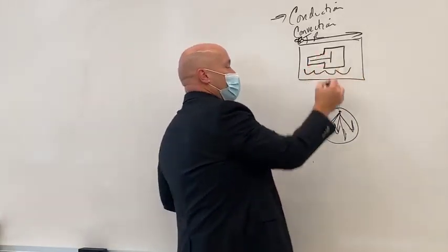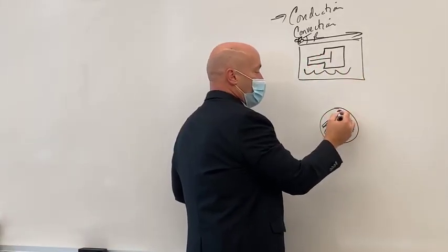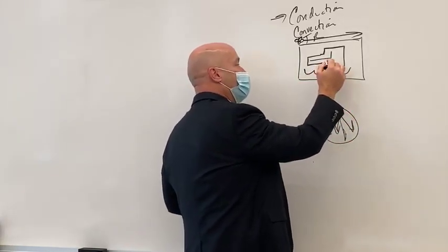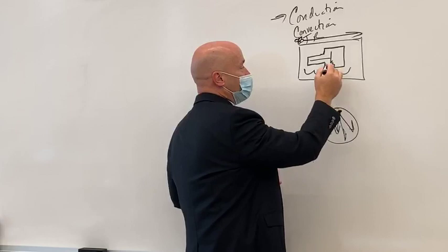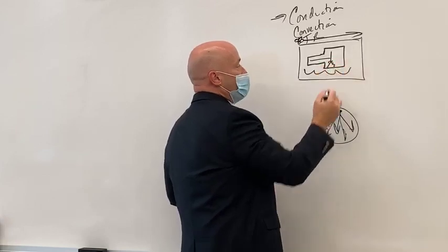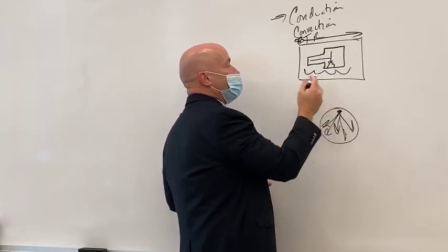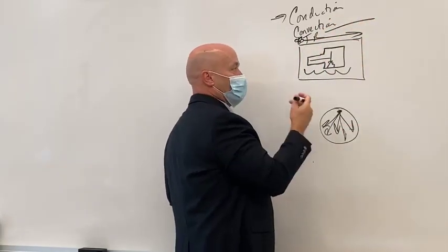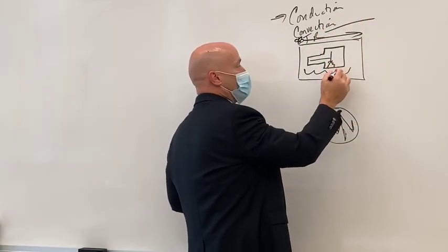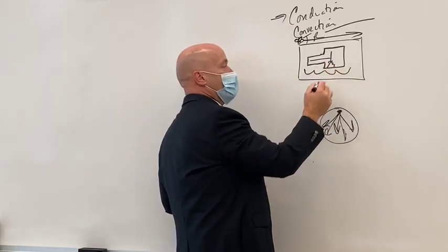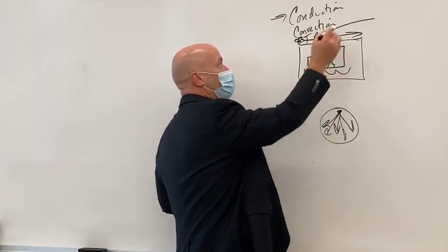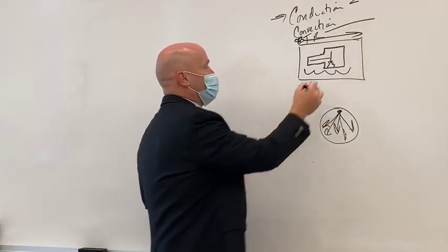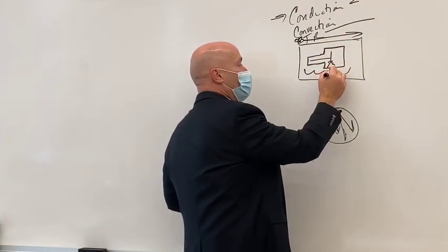And so we've got the conduction from the actual focal spot across the face of the anode, and then it's going to thermally radiate to the glass. And so that is your thermal radiation, one place we have thermal radiation. So it goes to the glass, but the glass is in contact with the oil, so we are back to conduction. In the second place, we get conduction from the glass into the oil.